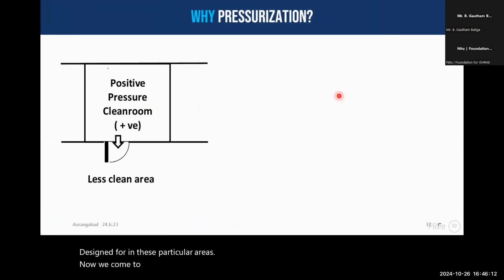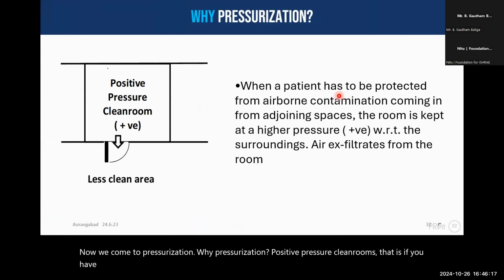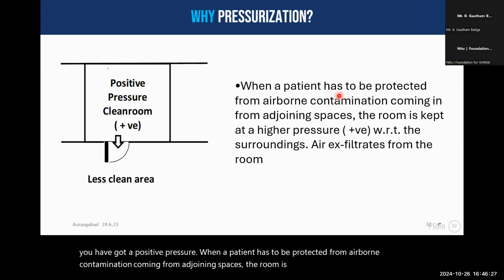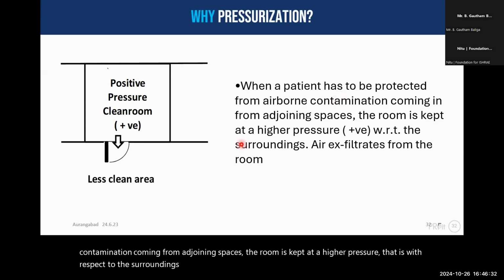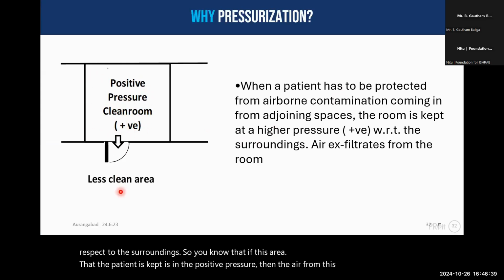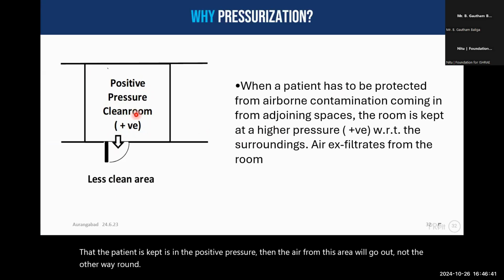Now we come to pressurization. Why pressurization? Positive pressure clean rooms. That is, if you've got a positive pressure, when a patient has to be protected from airborne contamination coming from adjoining spaces, the room is kept at a higher pressure, that is with respect to the surroundings. So you know that if this area where the patient is kept is in a positive pressure, then the air from this area will go out, not the other way around. So air only exfiltrates from these rooms.